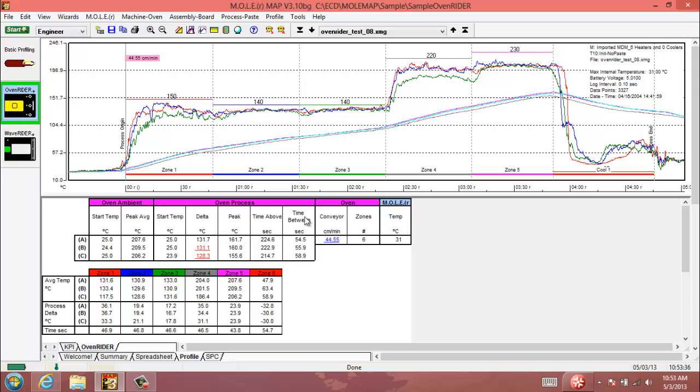The time above and time between figures here are values that are entered when you create a new oven rider environment. These values are for the process sensors themselves, which, like I mentioned, never saturate. They're designed to never saturate in temperature throughout the entire oven run. So these are customizable values for temperature which you would enter when you create an oven rider environment.